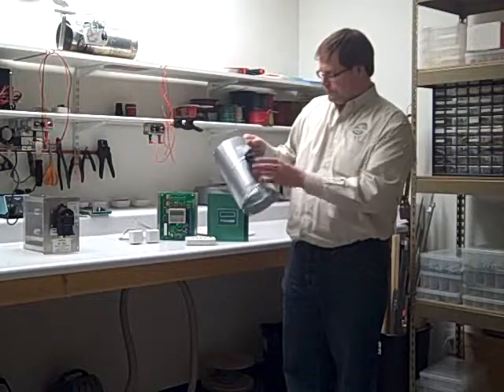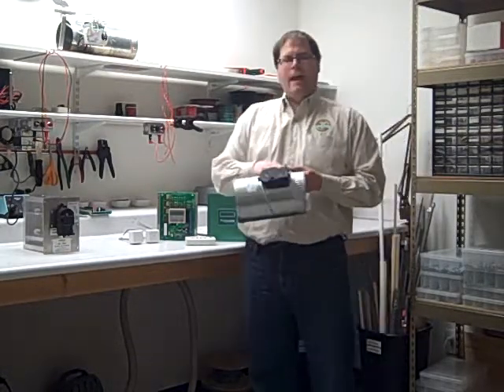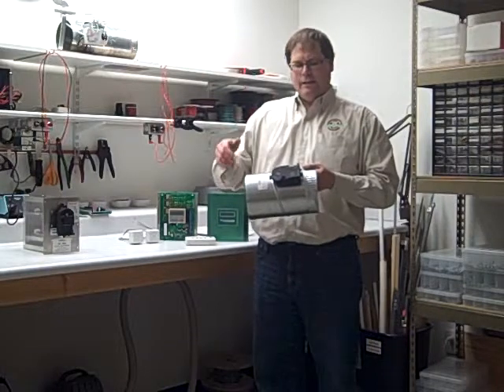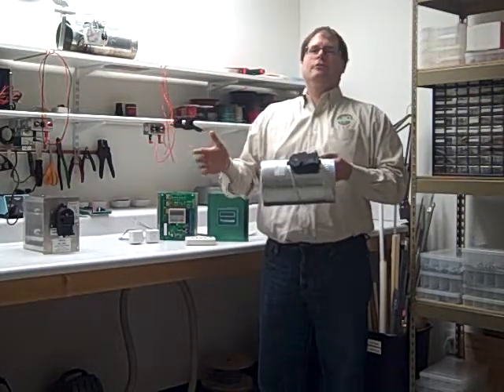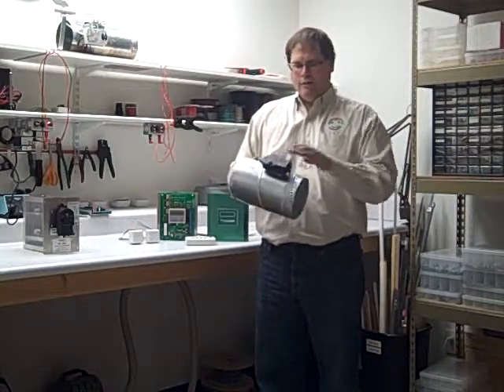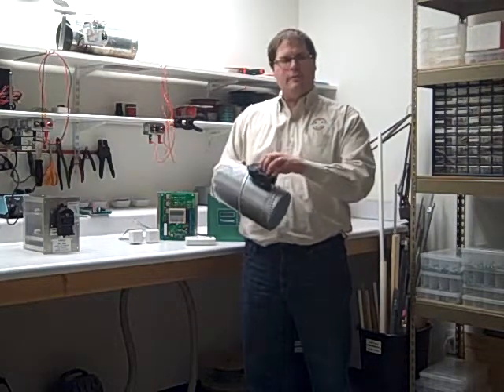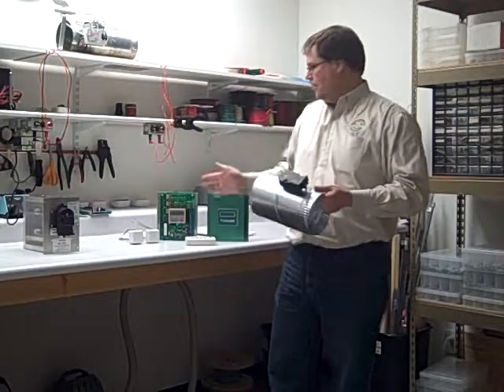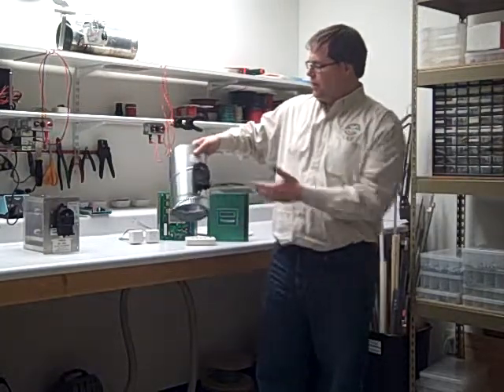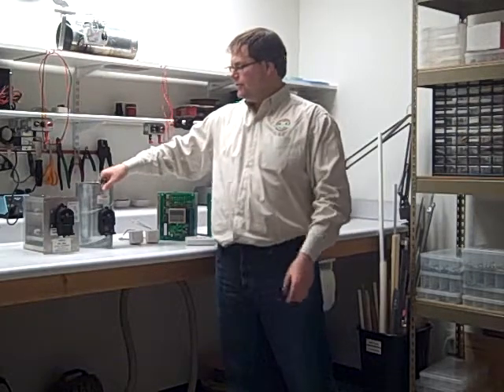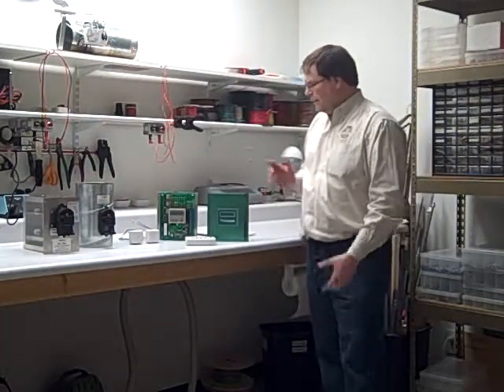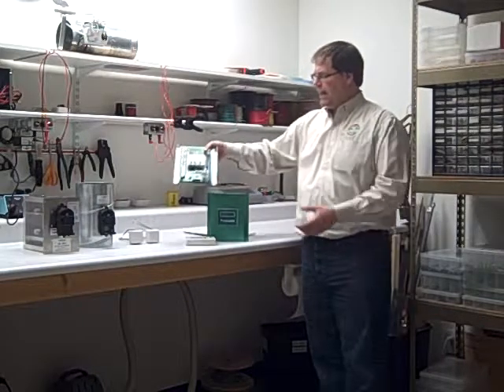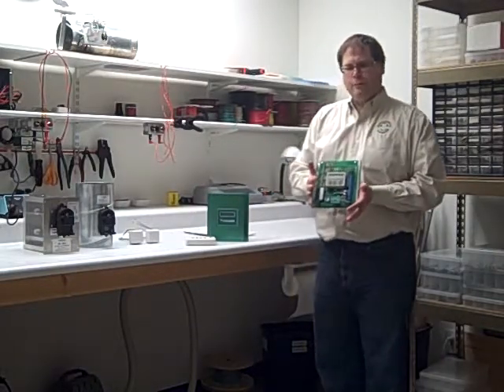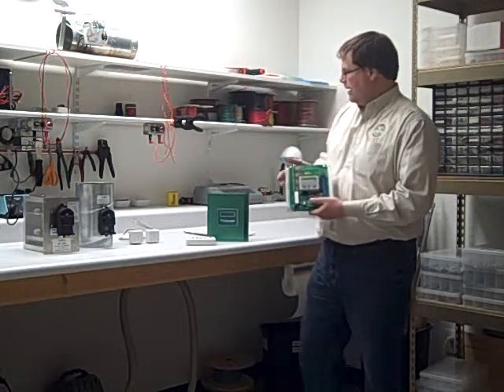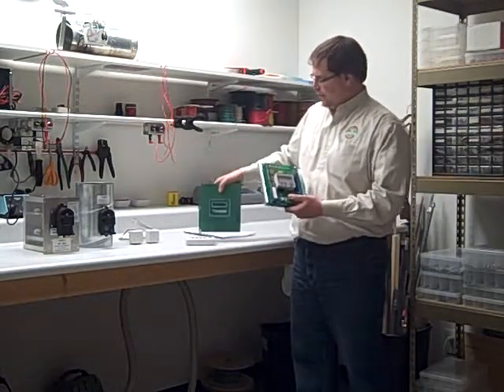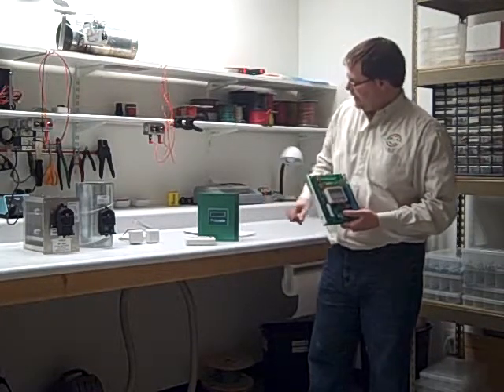So that's how the actuators work, and no problem in having multiple actuators per zone. So if you needed 5, 10, 15 actuators per zone, because of how the ductwork's laid out, you address each of the zone dampers with the same number, and they would all communicate in harmony back with the panel itself. So whatever size damper you're going to need, we're going to have those in stock. Next, let's talk a little bit more about some of the features on the panel itself. You'll notice the real small footprint again. Easy design. It does have our new design of cover with the snap-on green anodized cover.